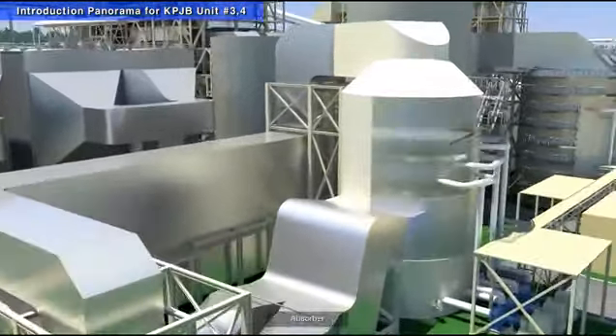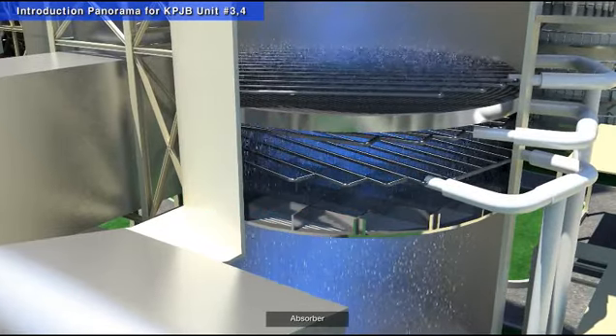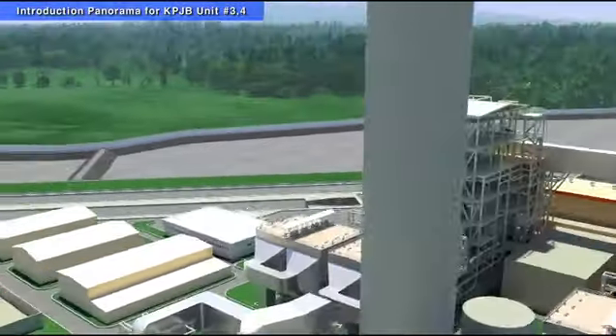Sulfur dioxide of the exhaust is removed by the flue gas desulfurization. By passing the boiler exhaust gas through the absorber, the sulfur dioxide gas of the exhaust gas and the limestone slurry which is sprayed from the top of the absorption tower react with each other, so that the slurry absorbs the sulfur dioxide gas and thus discharges clean gas without sulfur dioxide.